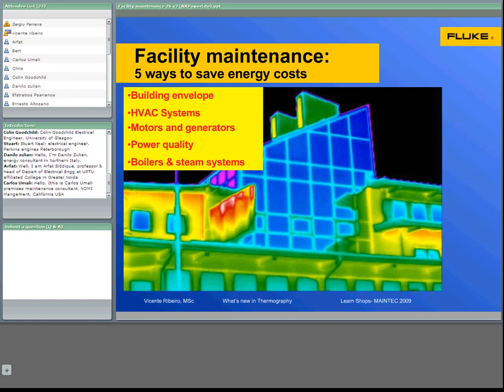Now here is an equipment, and transformers also suffer a lot from harmonics. In this case we have problems. One problem with harmonics and another problem with the circulation. That is, the oil in the transformer is not circulating properly, is clogged here. But harmonics in the transformers can reduce the lifetime of a transformer from 30 years to 7-8 years with enormous costs.